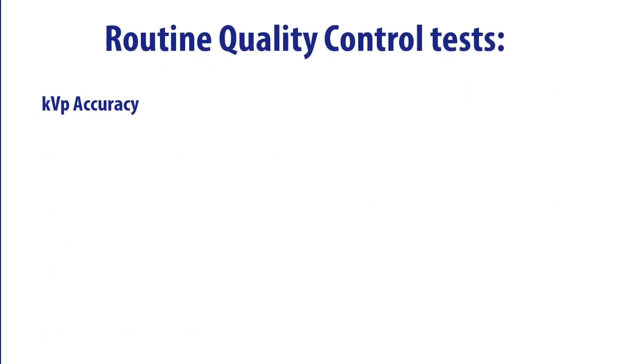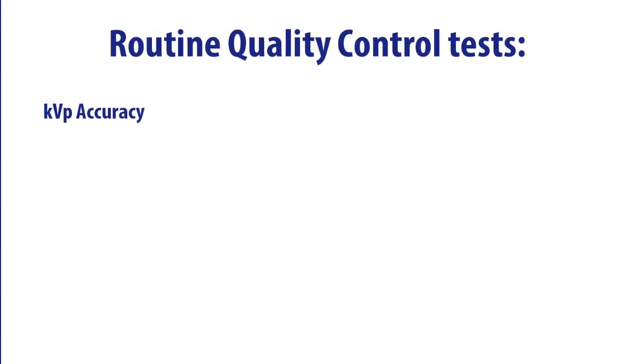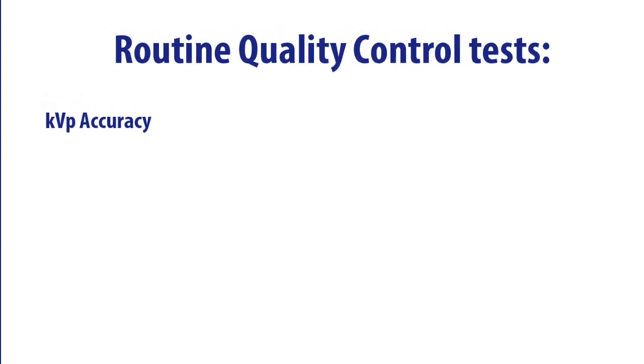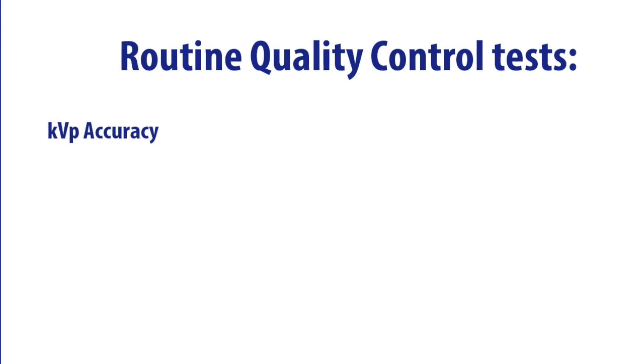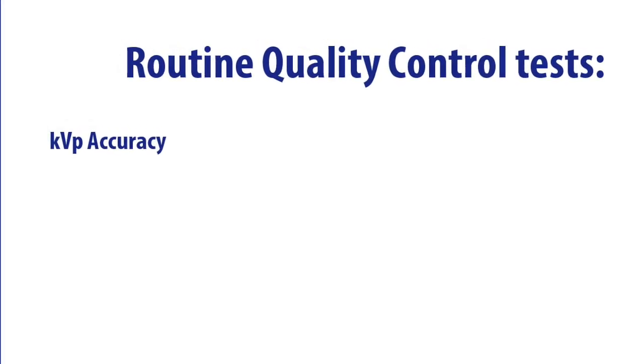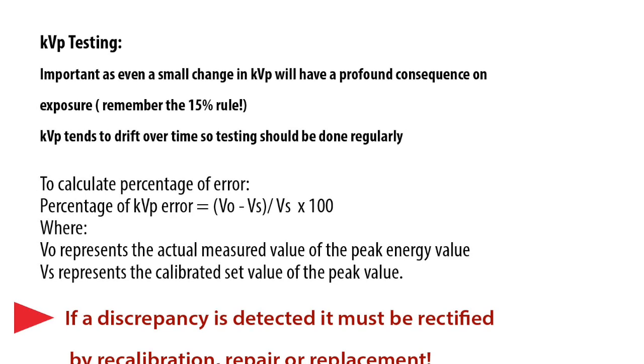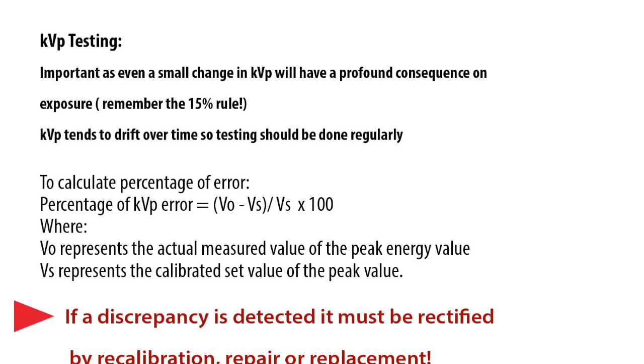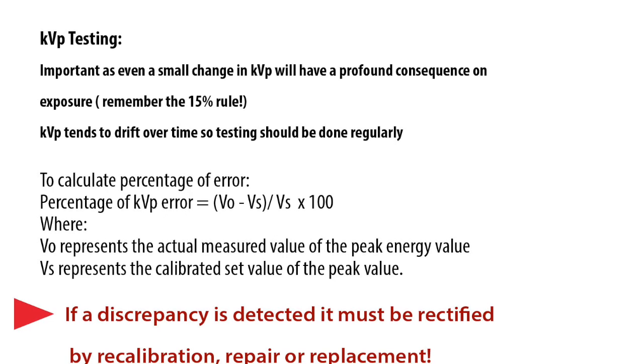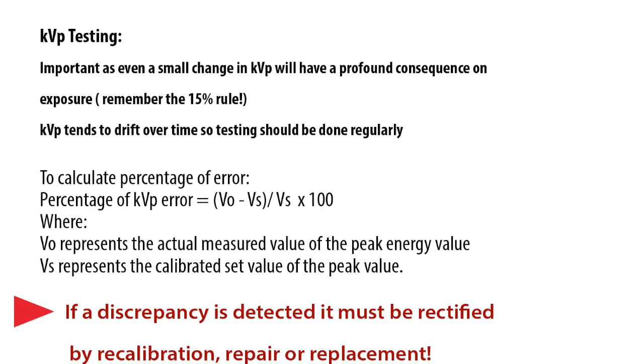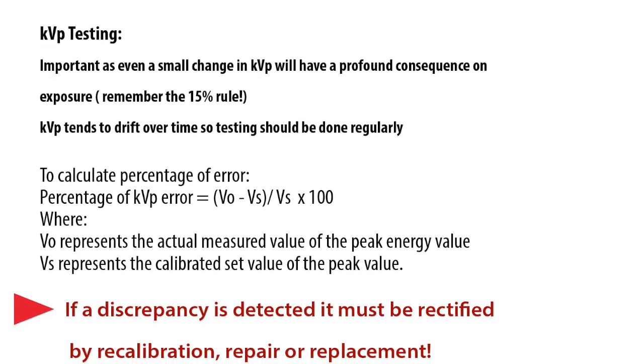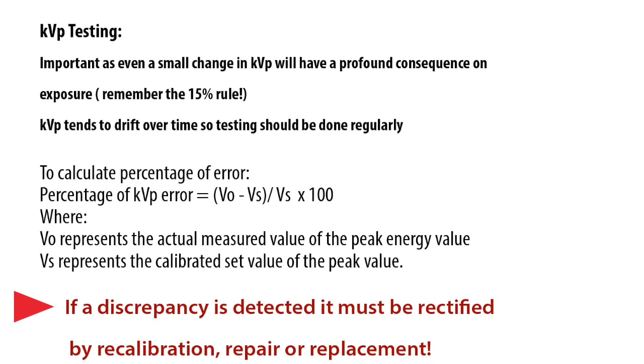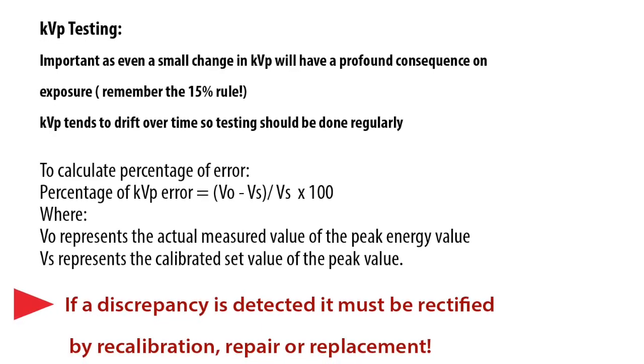KVP needs to be routinely checked as the actual values tend to change over time as a function of normal wear of the tube, resulting in damage to the tube itself and/or components such as the filaments, bearings, anode, etc. These changes, as well as other latent failures, can result in unpredictable output KVP production, which can yield unpredictable results manifested as unacceptable contrast and image receptor density and can ultimately result in repeated exposures.